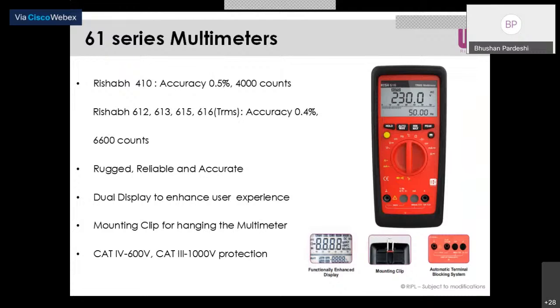First we should understand average measurement, RMS, and true RMS measurement. An average measurement multimeter calculates only the first half of a cycle and gives the average reading of the sine wave in one cycle. An RMS value gives an equivalent DC value of the sine wave. But a true RMS multimeter considers the harmonics contained in the waveform and their effect, giving a reading that includes the effect of harmonics in the system.